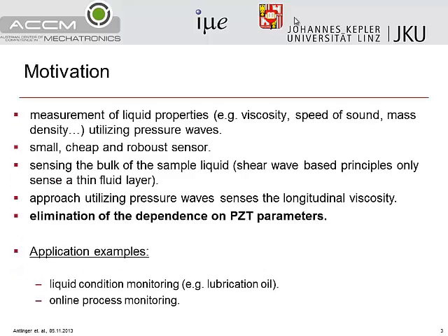So what was the motivation of our work? The measurement of liquid properties, like for example viscosity or mass density, utilizing pressure waves. We are looking to get a small, cheap and robust sensor. And what we also want to do is sense the bulk of the sample liquid. Shear wave approaches, due to the small penetration depth, only sense a small area around the sensor, and with a pressure wave approach we can sense the bulk of the probe.